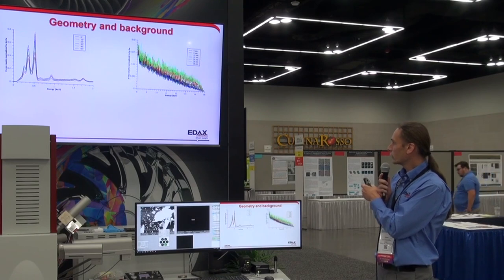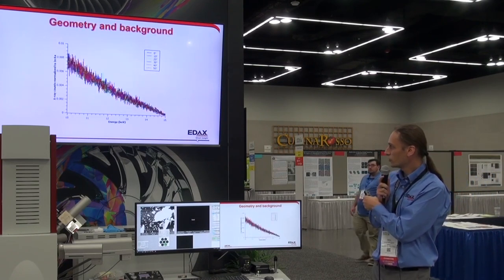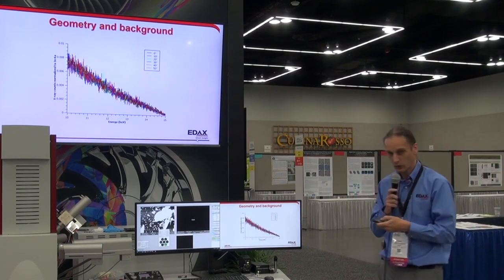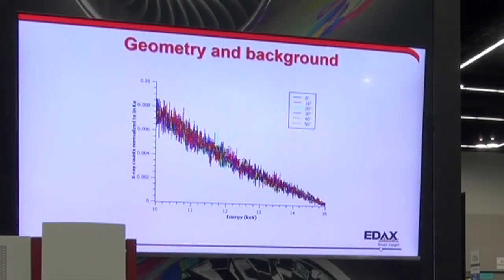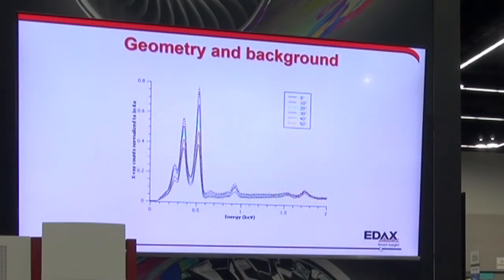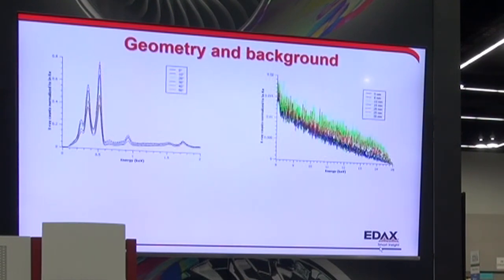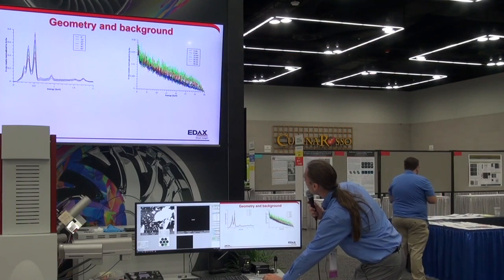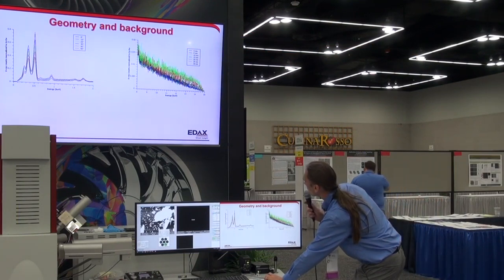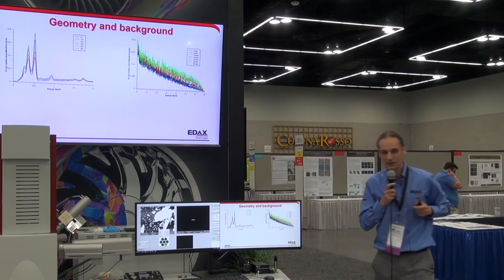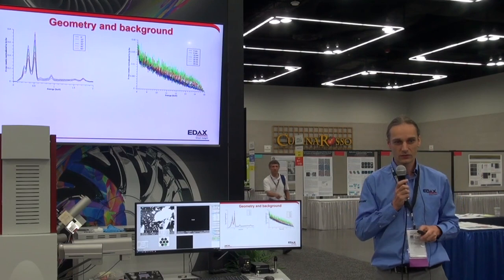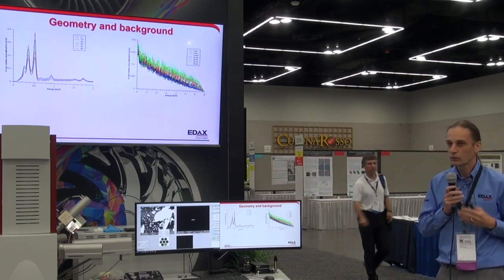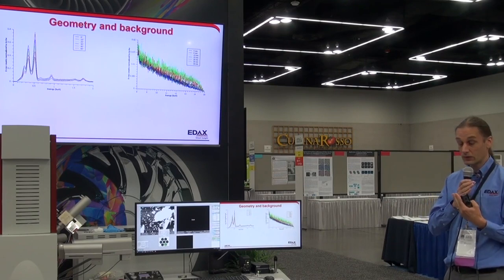One thing I want to point out: there is no change in the background tail when I tilt for the conductive sample — everything trails off towards 15 kilovolts. But at very long working distances, 25 and 30 millimeters, you can see a slight increase and a bump out in the high energy range. That's not x-rays — that's actually electrons getting into the detector. This is one of the reasons why we recommend staying close to the intersection distance of the detector.